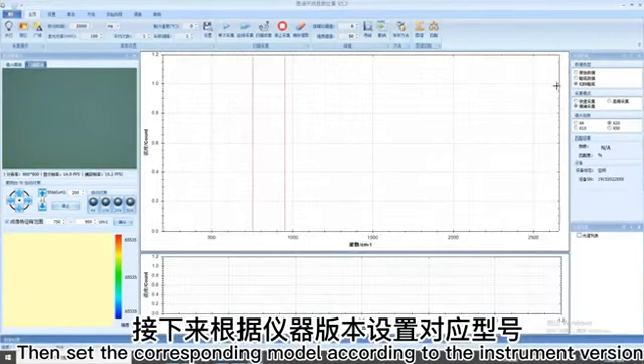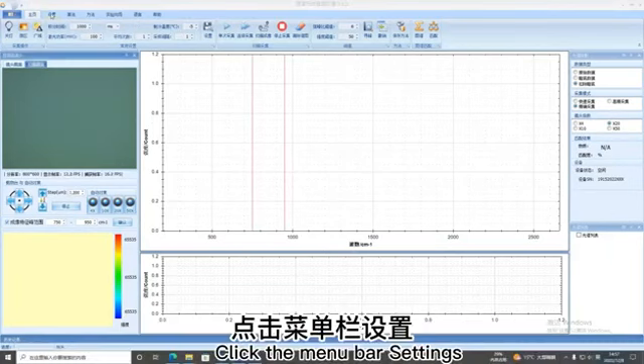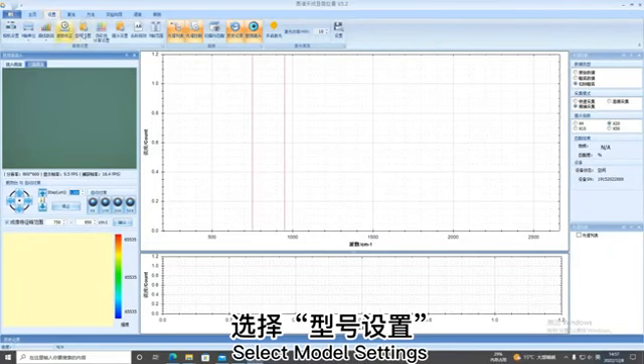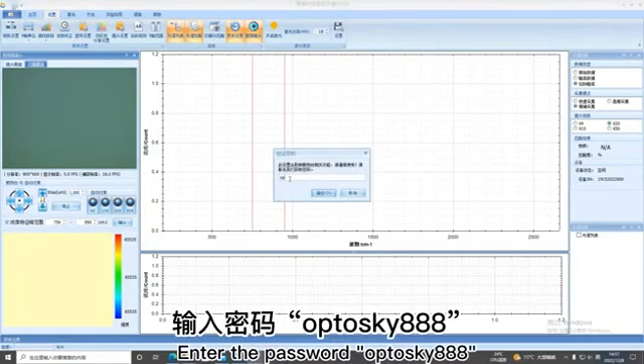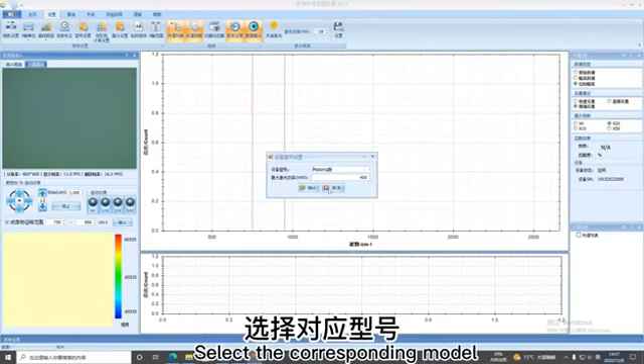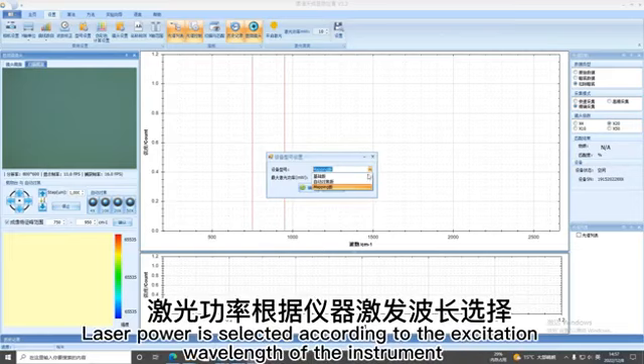Then set the corresponding model according to the instrument version. Click the menu bar Settings. Select Model Settings. Enter the password. Click OK. Select the corresponding model. Laser power is selected according to the excitation wavelengths of the instrument.